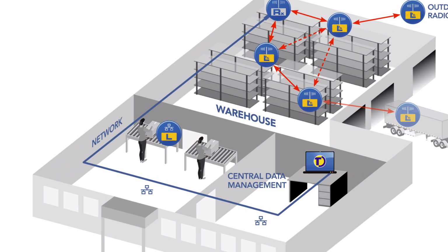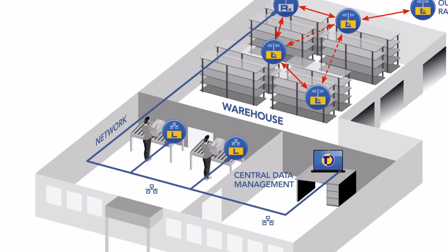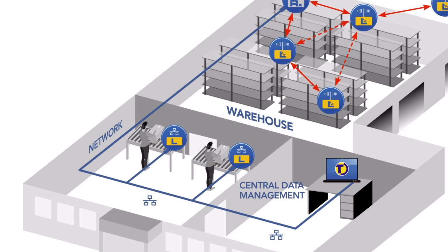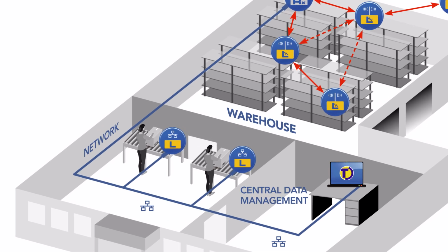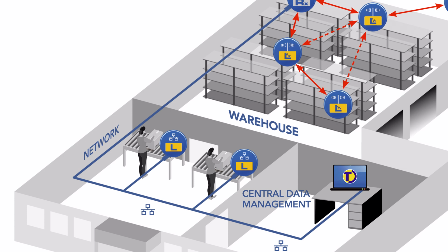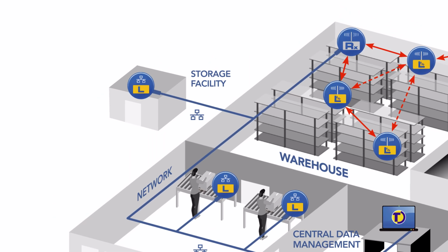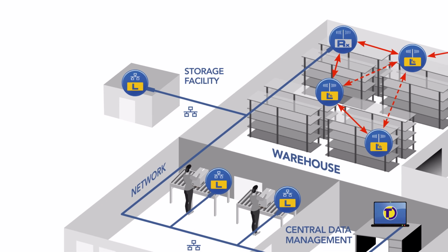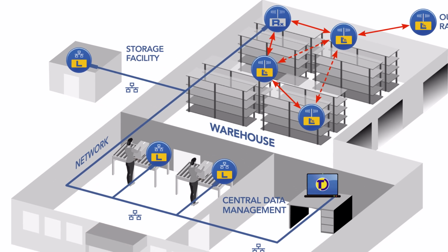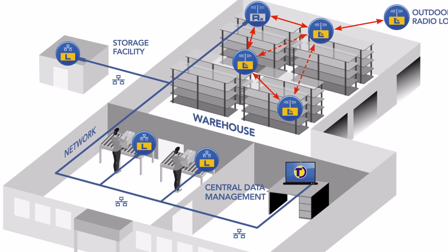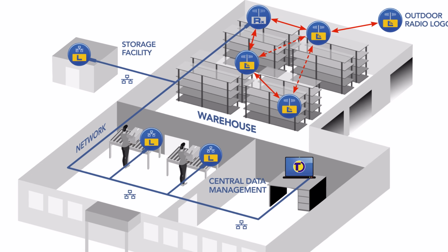Tinytag Plus LAN loggers plug into a network point, recording and sending data across a LAN for viewing in Tinytag Explorer Connect. They are powered through their LAN connection, and battery backup will keep the logger recording if this should fail. They can be placed wherever a convenient network point is available and are ideal for locations where radio signals may be problematic due to range or physical obstructions. Both radio and LAN loggers will keep recording in the event of communications problems and will transmit their data when the connection is restored. Email alarm notifications can be generated if conditions fall outside user-defined limits.